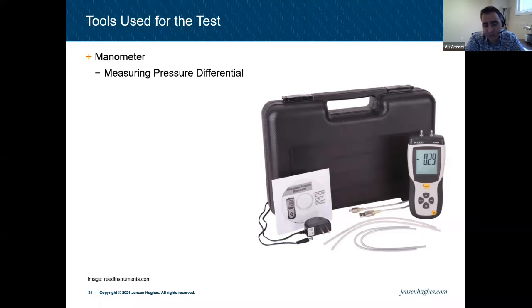So in the SB4, there are some numbers that we need to follow. Let's say for a Means of Egress vestibule, they're asking for 12 Pascal pressure differential. So it means when your Means of Egress vestibule is pressurized, the pressure in that area needs to be higher by 12 Pascal than the adjacent floor area, just to make sure the smoke cannot get into that vestibule. Which again is one of those things that you don't see very often, because usually these Measure N vestibules have just a little fan there. And I don't know if the 12 Pascal was never measured there or whatever the reason.